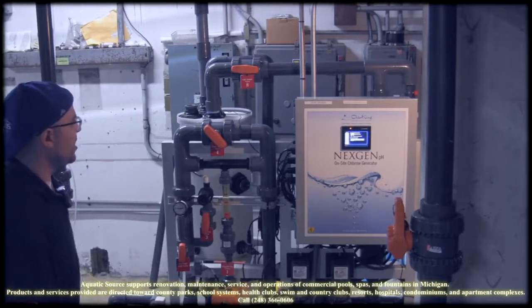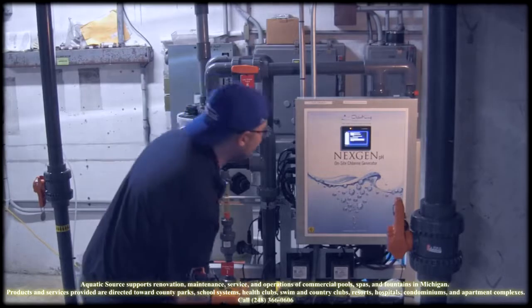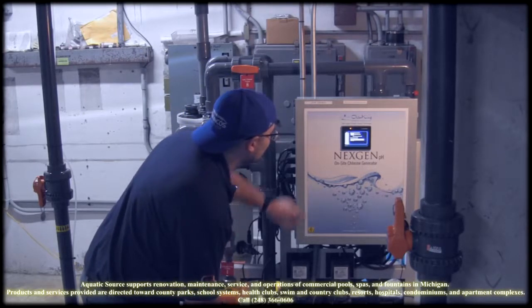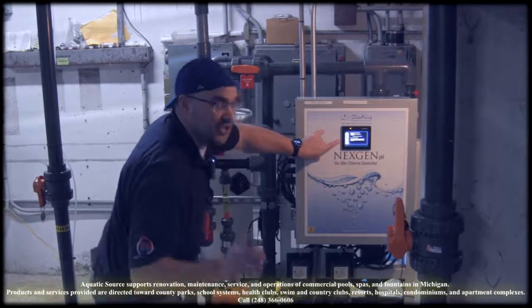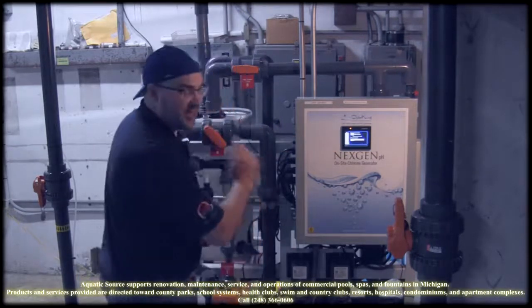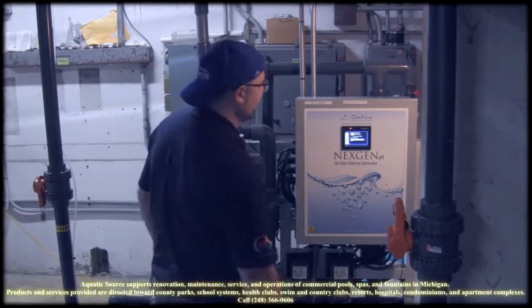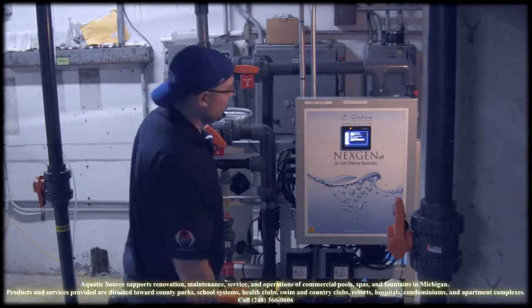So it's going to wait for the regen cycle. It's basically just waiting for the controller to call for chlorine. It's got a delay after it gets that signal, which is important so that I don't have the thing chattering on and off, blowing out contactors. It's going to wait 30 seconds after it gets that signal from the controller. You can override that on the screen.